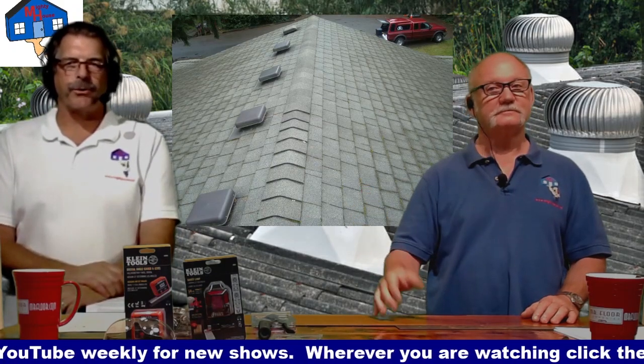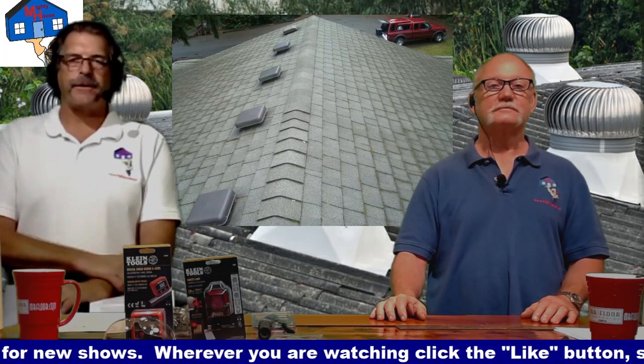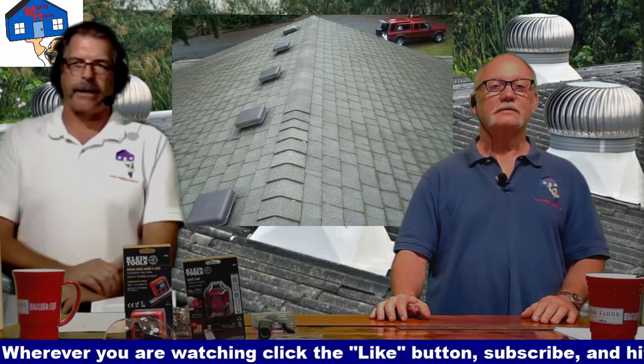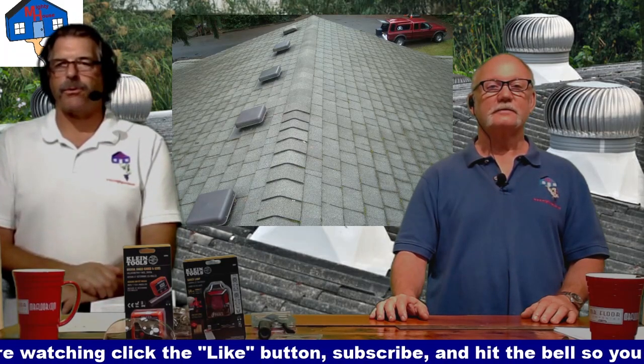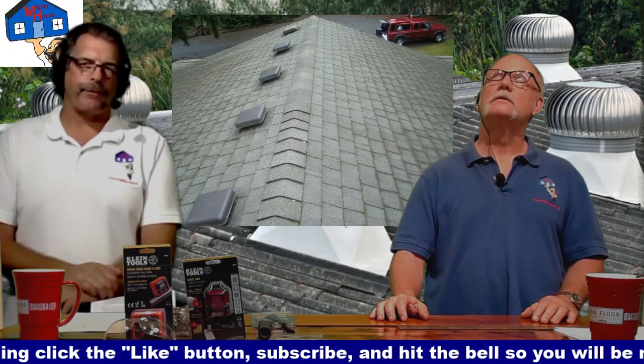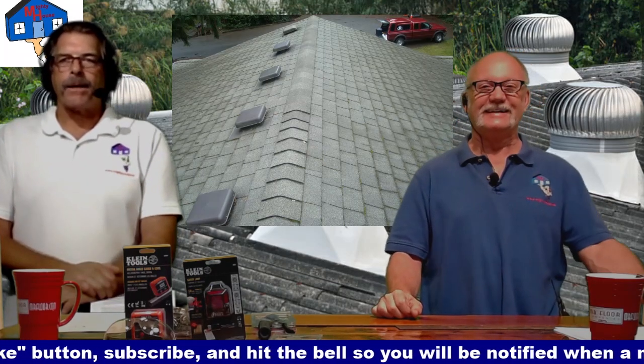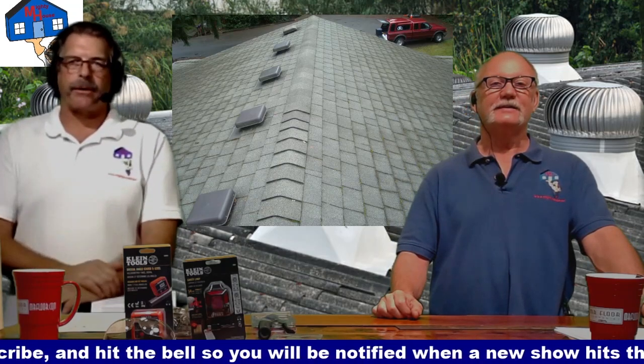Well, here's the thing. A mushroom vent in that style is typically right around 51 square inches of venting. Like you said, it'll be stamped right on it. 51 square inches. Well, what's a square foot? 144 square inches. So to make 1 square foot, I need almost 3 of those.